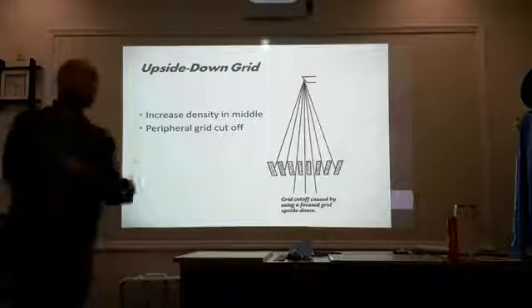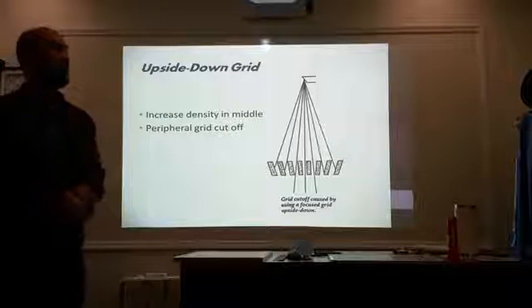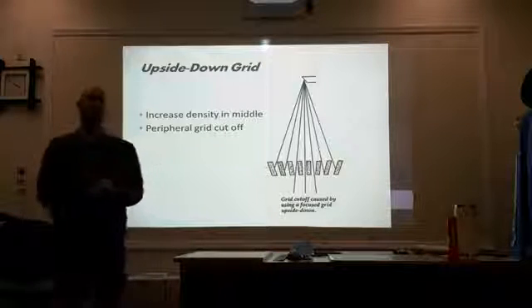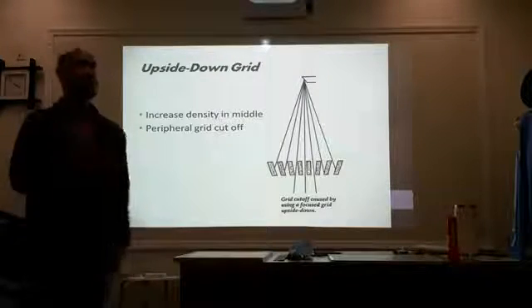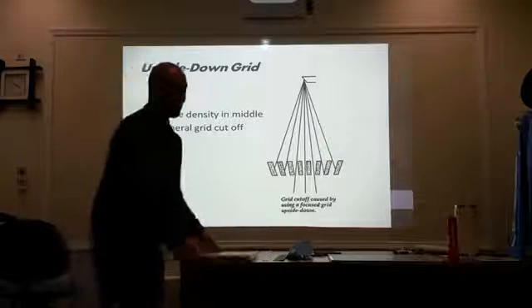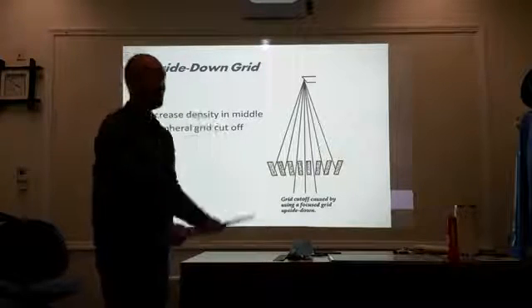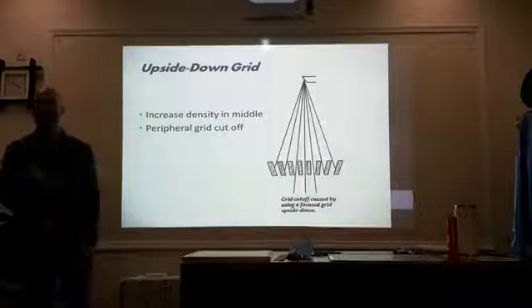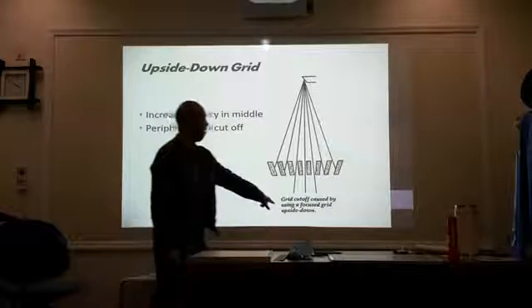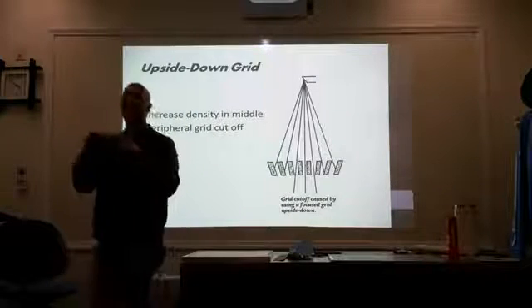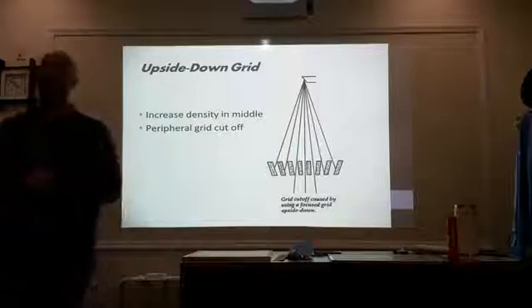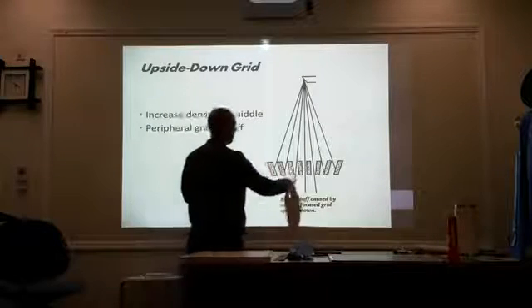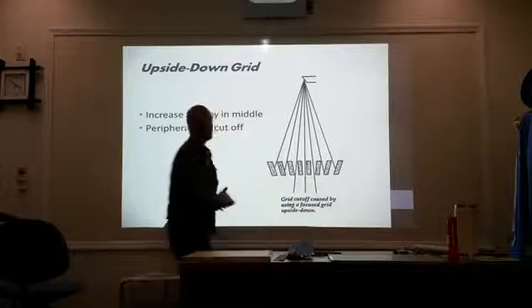Upside-down grid. You're working so fast, you just had a bad day at work, you're not thinking straight, you haven't had lunch yet. You're going to shoot your portable, you put your grid underneath, but you're not paying attention whether it's upside down or right side up. Are you still going to get an image? You're still going to get an image, but you're going to have grid cut off or decrease in density on the periphery of your image. Notice that the slant is going the other way, doesn't match the divergence of the beam.